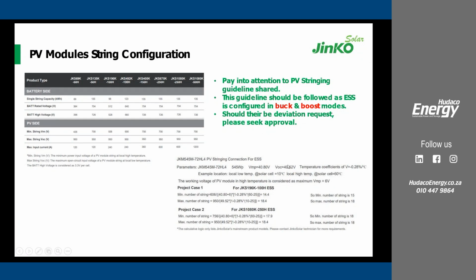We've also given a guideline on how you can use our standard modules, or any other modules, to calculate this—using the temperature coefficient to calculate the actual voltages on site, so you can determine how many modules you require in one string to achieve the required voltage. I'm not sure if there's any question on this point.